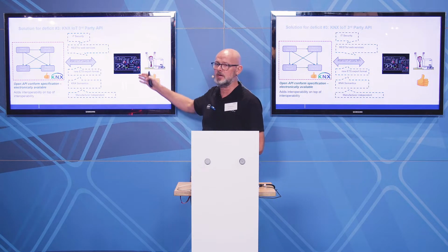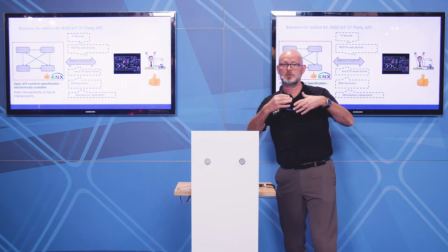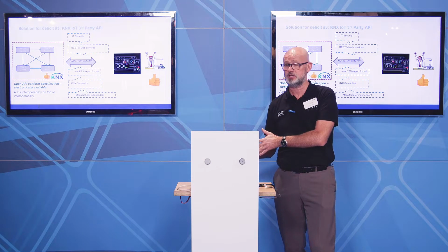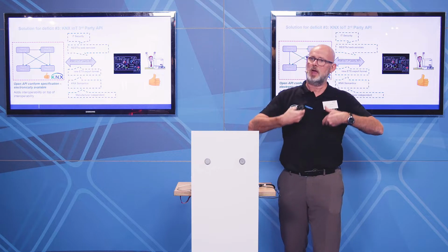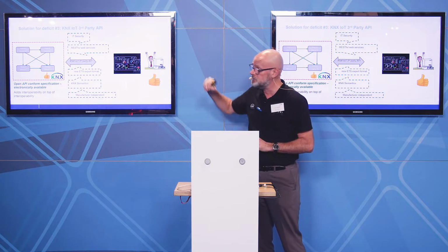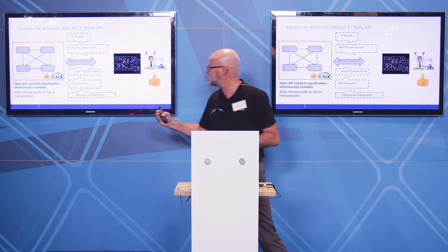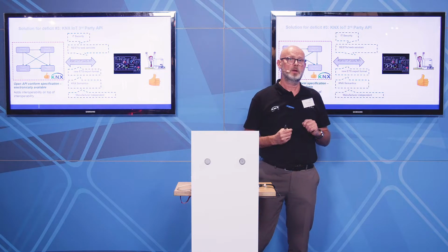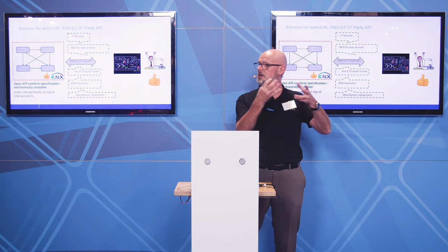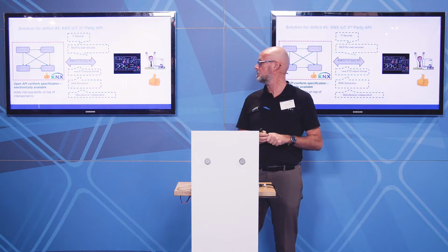So we needed a way of handing the data to an IT guy. Mostly these are IT guys that develop such visualization software. We needed to offer this in a modern way, not via KNX Net IP, which is a UDP frame, but with HTTPS, so in a secure way with RESTful web services. And we also needed to add meaning to the data. So the recipient of the data must understand, this is a light in the kitchen. This is a temperature. It's an outside temperature.